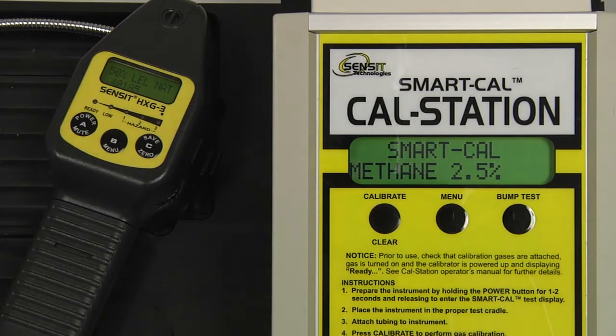Once a stable reading has been achieved, data saved will be displayed on the instrument, and pass will be displayed on the cal station. The number on the display of the instrument is the raw output of the sensor, and is useful as a reference when troubleshooting if any issues should occur.